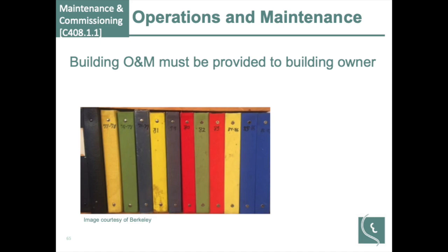I don't know if it was in ASHRAE 90.1 or a white paper, but somewhere there was a recommendation or requirement that could meet that part of the code if you put a nameplate on the equipment that included the O&M documentation, like this size belt gets on this area. So that could be a means to meeting that, just requiring a nameplate or a maintenance plate be added near the equipment that includes O&M information.